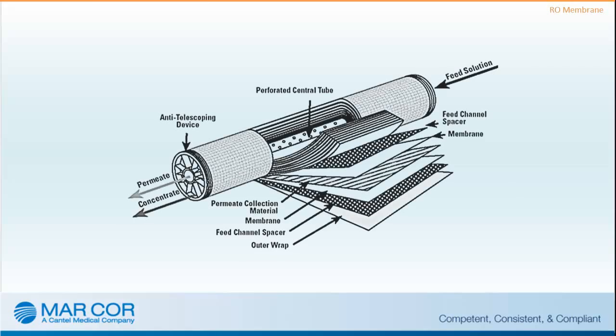The RO membrane consists of interleaved layers of spacer, membrane, and permeate or product water carriers. This spacer allows for the movement of the concentrate past the membrane, and the permeate carrier carries the purified water out of the element. The CWP unit removes at least 95% of the total dissolved salts and more than 99% of the bacteria and endotoxins from the inlet water.